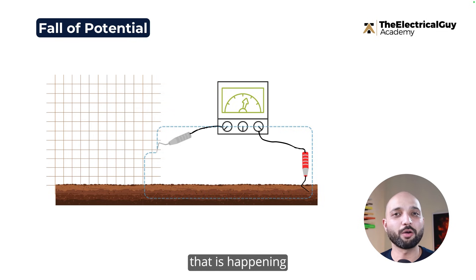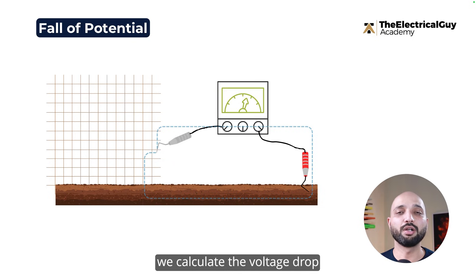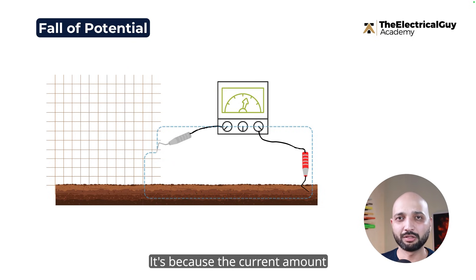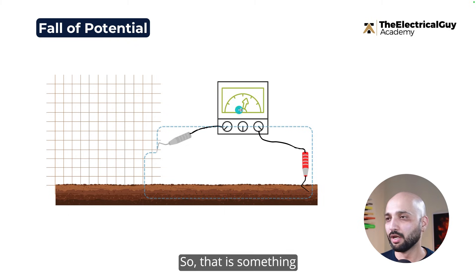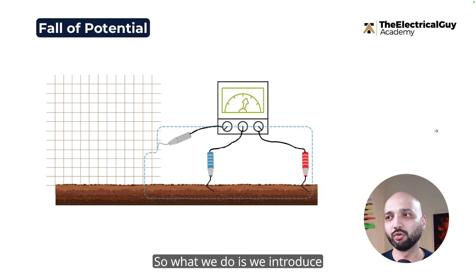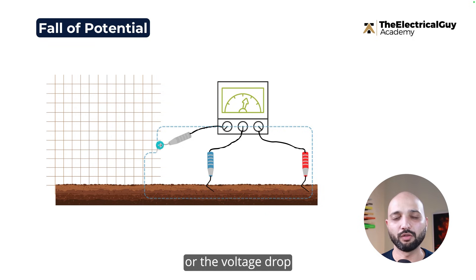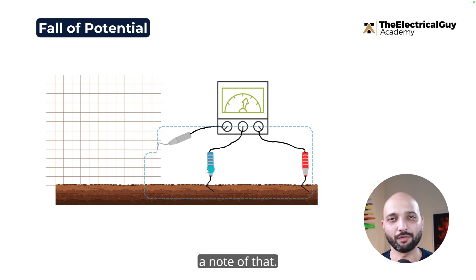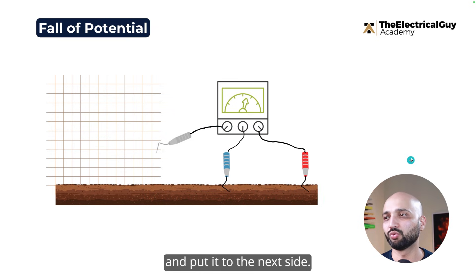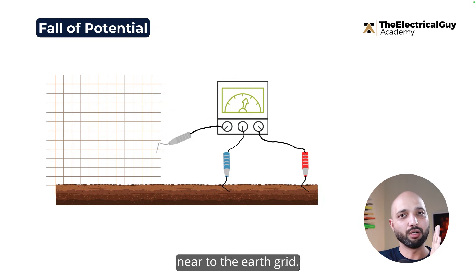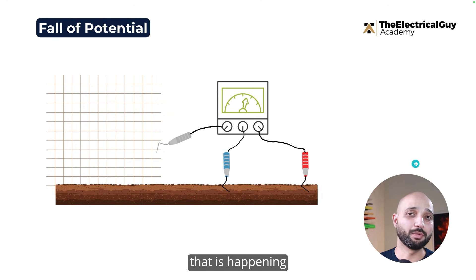We need to measure the voltage drop happening between two points so we can calculate the resistance. We know the current we are passing, so based on that we calculate the voltage drop and then the resistance. To do this, we introduce a third electrode — a potential electrode — placed in the ground closer to the grid. We then measure the potential drop between those two points, then move the electrode further away and take another reading.